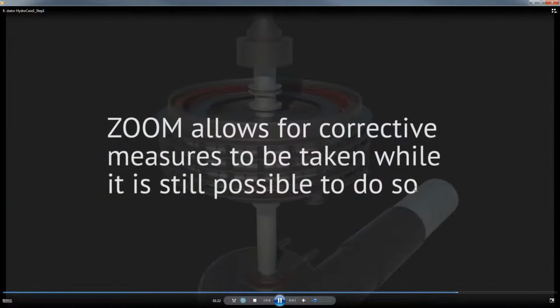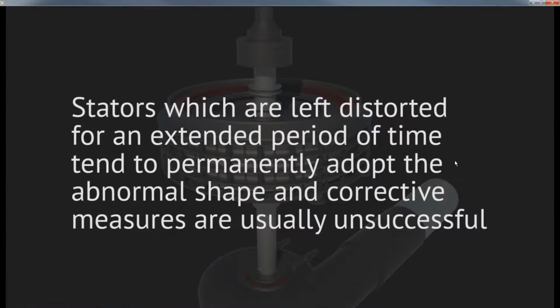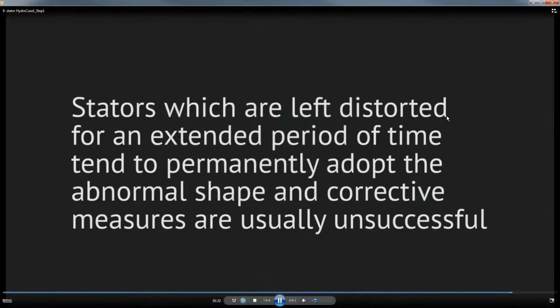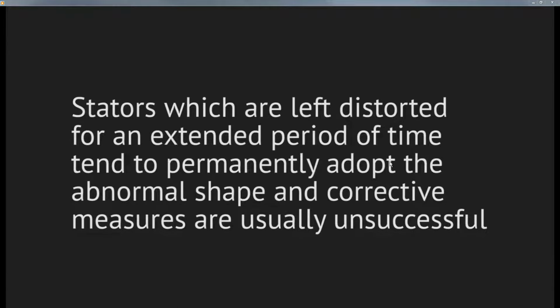Okay, so needless to say, the results were disappointing. The utility had to have serious discussions with the OEM to try to fix these issues. And as it says here, and I've seen this quite a few times, if the vibration is low, people will usually tolerate a stator that's out of shape, saying to themselves, well, we'll fix it in a year or two. Just put the unit back online and let's produce power.